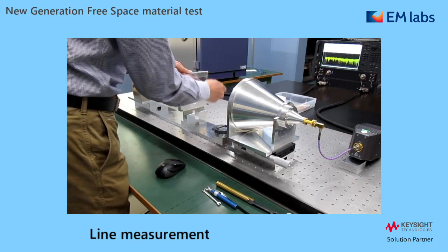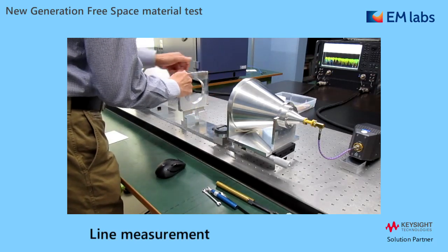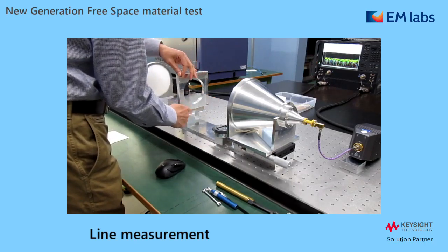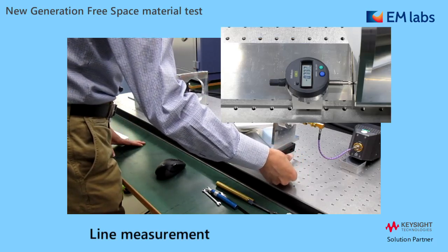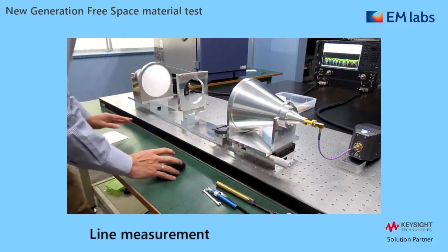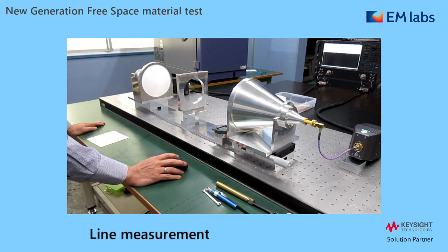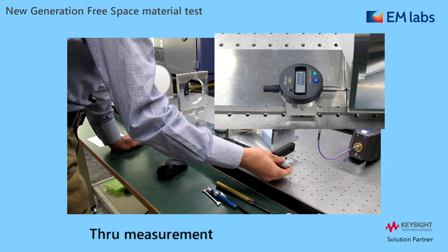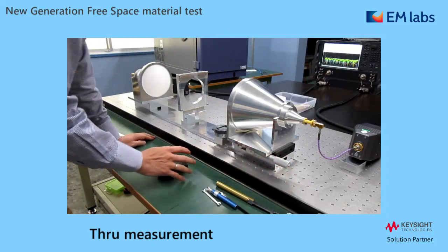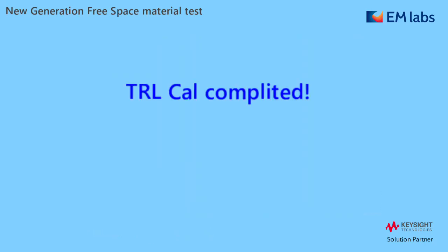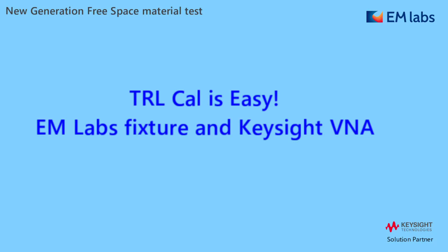The next step is line. Remove the plate first. We measure about a quarter wavelength in air, so change the antenna position accordingly, and trigger. Finally, for the through measurement, it's a direct connection, so just return the antenna position to 0 and trigger. Calibration is now completed. You can see calibration is easy with our fixture and Keysight analyzer.